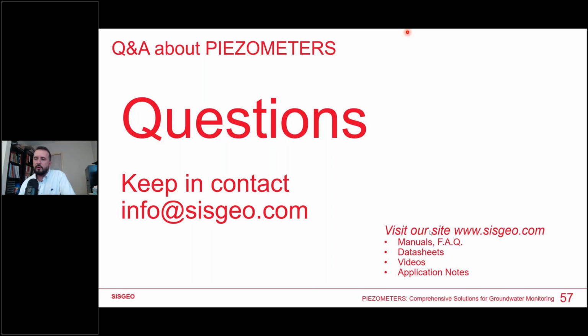Question, interesting. Is the accuracy of the 170 kPa probe similar to the 350 probe? So in percentage, it's the same. That means that the greater the range, the smaller the accuracy. That means a sensor with 350 kPa range is 2 times less accurate than 175, because the diaphragm has a different thickness.